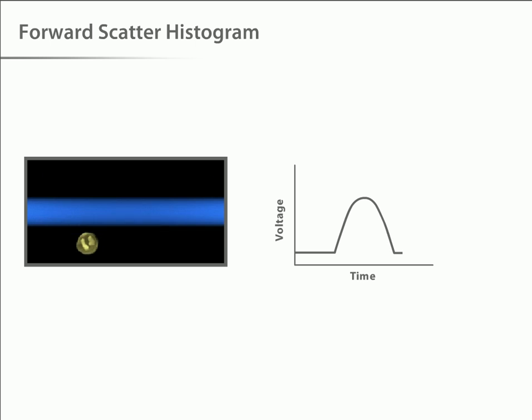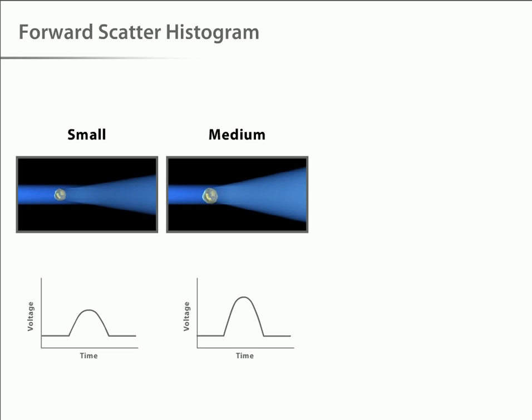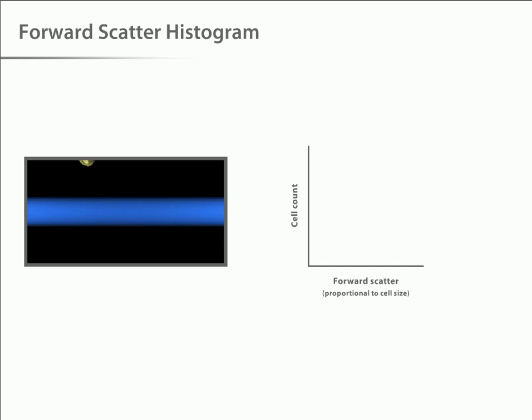The scattered light received by the detector is translated into a voltage pulse. Because small cells produce a small amount of forward scatter, and large cells produce a large amount of forward scatter, the magnitude of the voltage pulse recorded for each cell is proportional to the cell size. If we plot a histogram of these data, smaller cells appear toward the left, and larger cells appear toward the right.